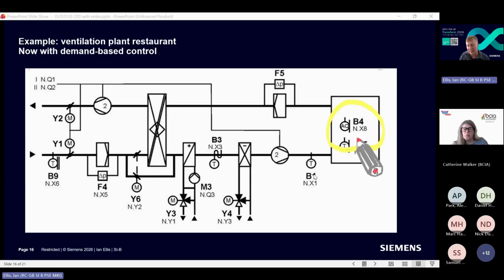But I add the additional sensor in there, this B4 sensor. So yes, there's a cost to add that sensor. There's the cost of the sensor. There's the cable back to the BMS, unless it's wireless, but then you'd still need some form of wireless gateway to pick up the information. That's another point on my BMS system, so I need to allow an I/O point, whether it's a module or an automation controller with onboard I/O. There's a bit of engineering required because I'd have to do something with that sensor input, and I'd probably add it to a graphic if I had graphics on the system. So yes, there's a cost, but what are the effects in terms of operational costs that adding that sensor will give me?